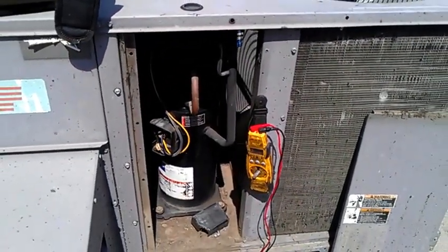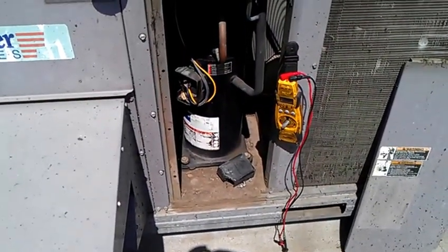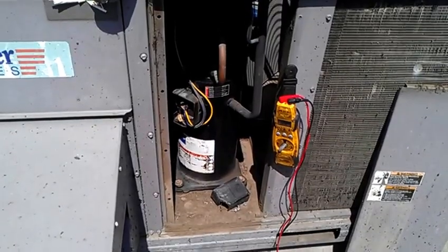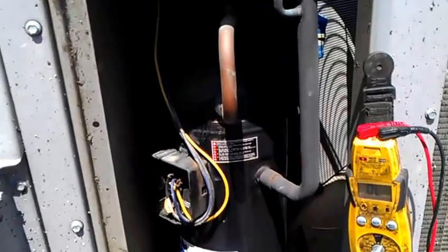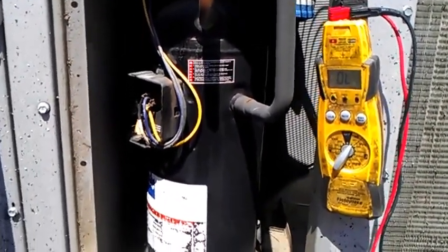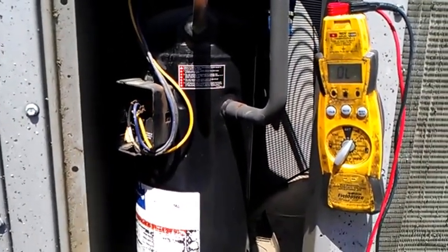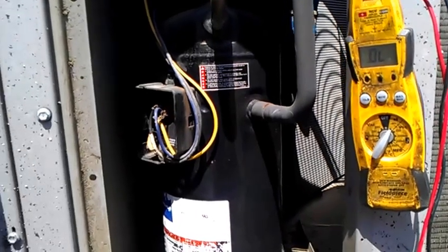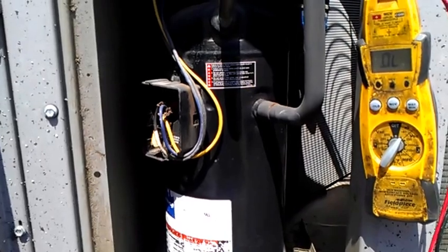We have here a three and a half ton compressor that is short to ground and tripping the breakers. This compressor was already failing, making a weird noise since last summer, and this is what happened in the end.